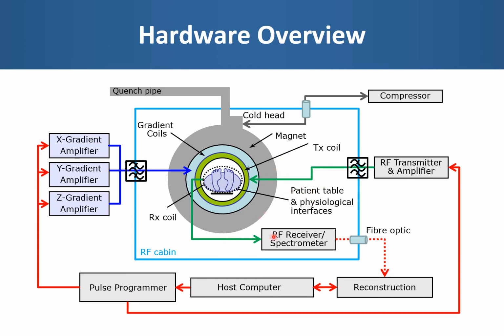The signals that are detected by the receiver coil go to this RF receiver and spectrometer, and they get converted to optical signals that are then passed through the RF cabin to the reconstruction computer, which performs a task such as the fast Fourier transformation that is used to reconstruct the images. The reconstructed images are then sent to the host computer for display.